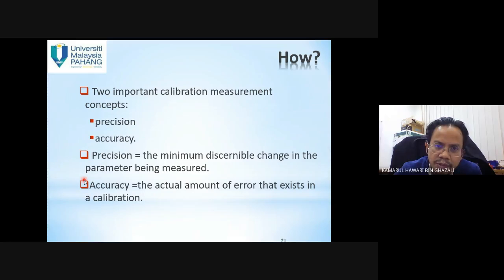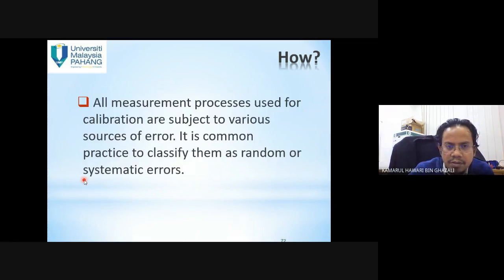Okay. The two important calibration measurement concepts are precision and accuracy. Precision is the minimum discernible change in the parameter being measured. Accuracy is the actual amount of error that exists in a calibration. So precision and accuracy are two important calibration measurements. All measurement processes used for calibration are subject to various sources of error. It is common practice to classify them as random or systematic error. So you can go back to the previous chapter to see the random error and systematic error.